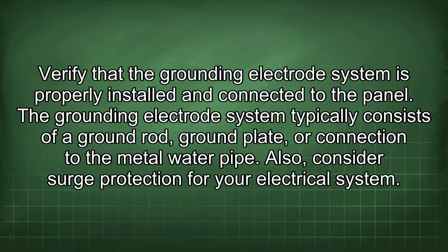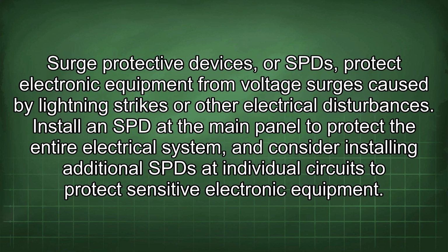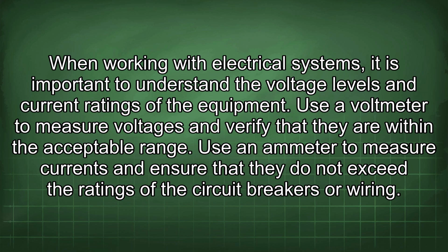Also, consider surge protection for your electrical system. Surge protective devices, or SPDs, protect electronic equipment from voltage surges caused by lightning strikes or other electrical disturbances. Install an SPD at the main panel to protect the entire electrical system, and consider installing additional SPDs at individual circuits to protect sensitive electronic equipment. When working with electrical systems, it is important to understand the voltage levels and current ratings of the equipment. Use a voltmeter to measure voltages and verify that they are within the acceptable range. Use an ammeter to measure currents and ensure that they do not exceed the ratings of the circuit breakers or wiring.